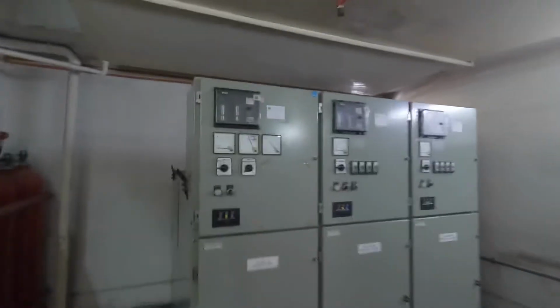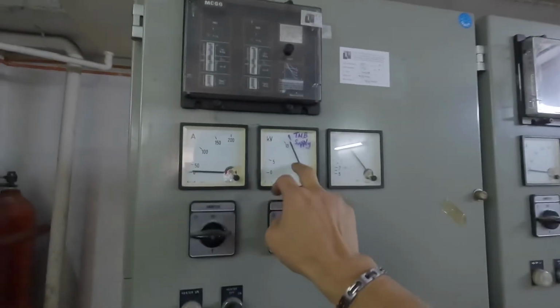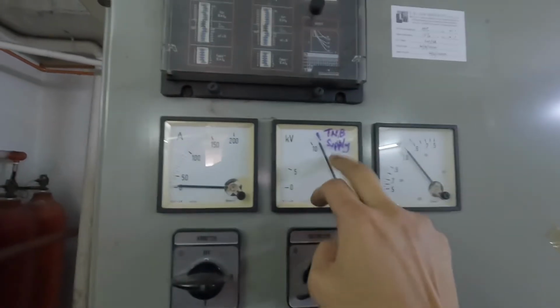Okay, after the genset has stopped automatically, so now we enter into the HV room. Okay, this is the HV room. Okay, first of all, this meter indicates that TNB power supply is available. Let's check the protection relay. Make sure all the protection relay is in good condition. Okay, and then here we have a tripping unit.